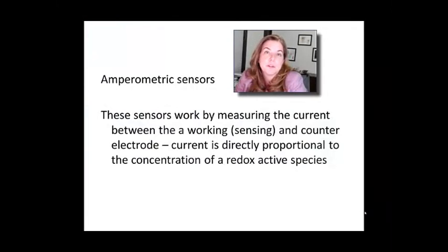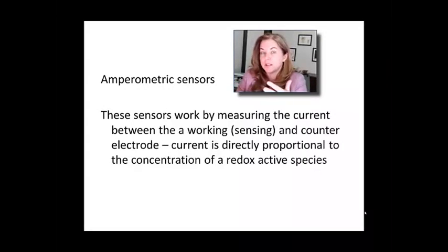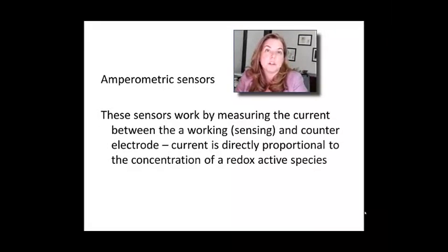An amperometric sensor, instead of measuring electrochemical potential, measures the current generated at a working or sensing electrode. A key difference is that electrochemical potential is proportional to the log of species concentration. In an amperometric sensor, current is directly proportional to the concentration of species in solution. That's potentially a problem for large dynamic ranges, but it has a different relationship to analyte concentration than potentiometric sensors.